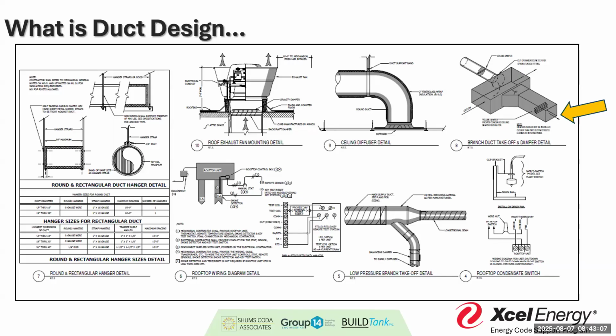How do I handle these transition spaces where we have a different takeoff? Some are round, some are square. That affects a lot of the design, especially when we talk about air velocity, dampers, and those kinds of things. We want that information as part of the process, so it needs to be part of the duct evaluation during plan review.